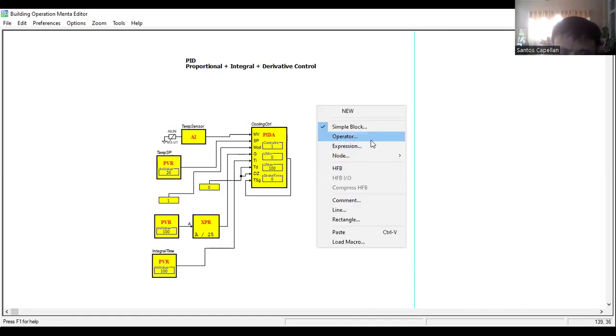Now here, we will use a switch. If there is airflow, then that's the only time we will activate our control. Meaning, let's say our air handling unit is working, if the fan is delivering air to the area being served, then that's the only time we will activate our analog output control.